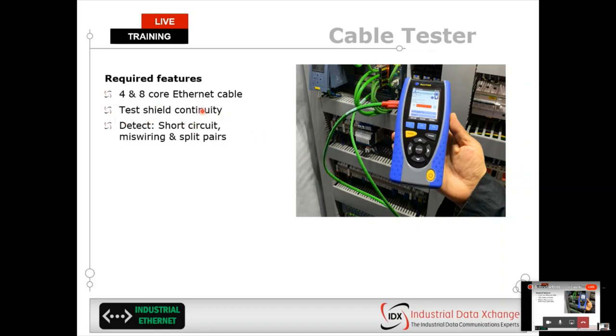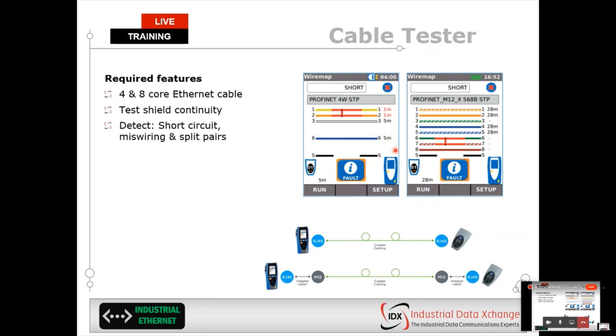It should definitely be able to test shield continuity, detect short circuits, miswiring, and split pairs between different components. What's very useful is it can even tell you what the cable lengths are. Remember we have that limit of 100 meters between any two devices, so the tester should tell you, oh wait, you're at 110 meters - this is a problem here.